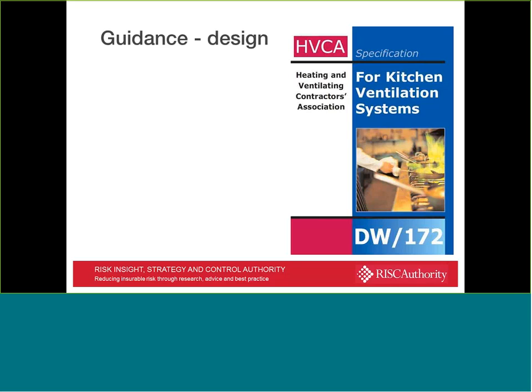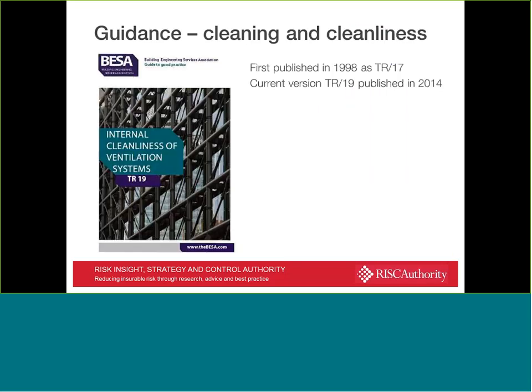Despite the fact there's design guidance for systems, doesn't always mean that systems will be designed and installed to the standard. I think that where systems are being designed into a new build or a significant refurbishment, it may be far simpler to design in accordance with the standard than it would be if you're retrofitting into an existing space where you may not necessarily be able to meet all of those design requirements. So despite the fact you may be told that the system was designed and installed in accordance with the specification, in much the same way as we might ask on inspecting a premises to see the completion certificate for a fire detection and alarm system, which will list any deviations from the standard, it may also be worth asking a very, very similar question in terms of design criteria, just so it's easier to understand exactly how the system's been designed, whether there are any significant anomalies from the design criteria.